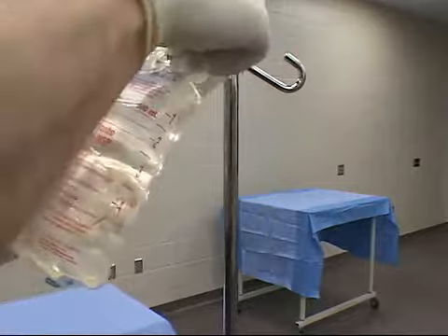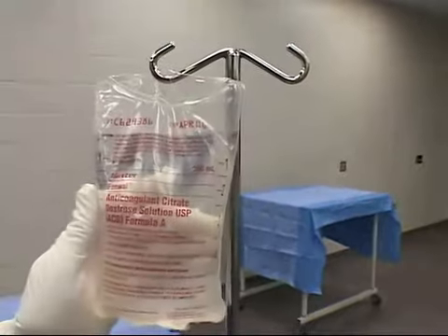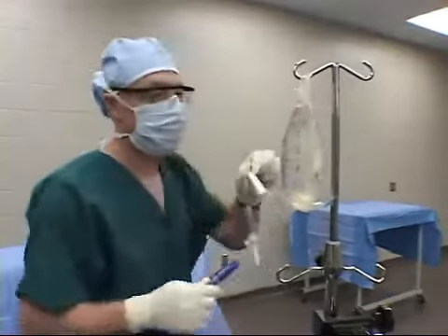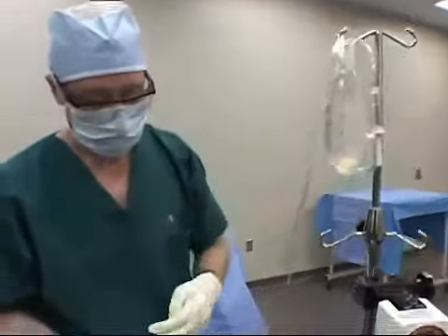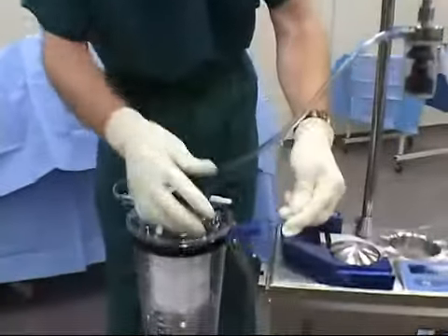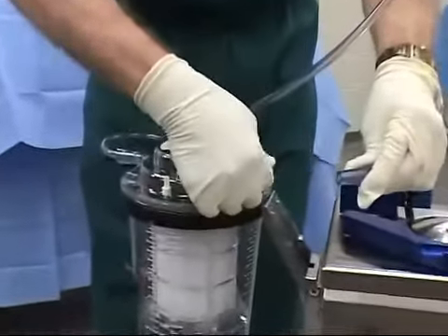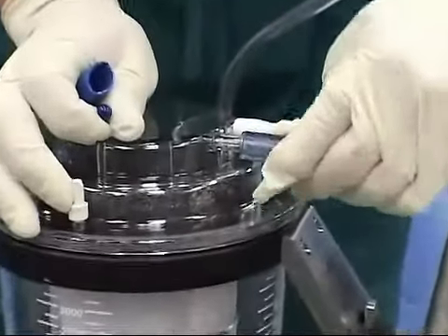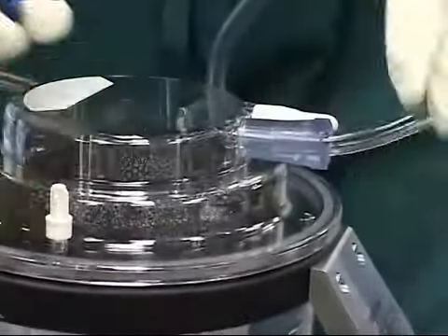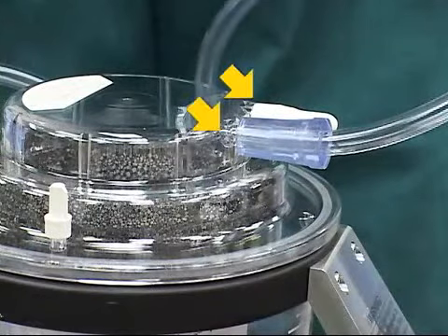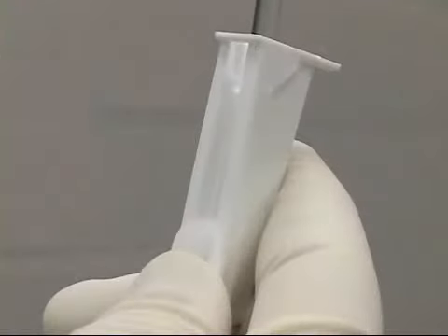Hang the anticoagulant solution on the upper IV pole. Attach the blue-capped end of the suction anticoagulant line to either the blue or the white inlet port of the reservoir. There are two inlet ports available to accommodate multiple suction lines. Close the roller clamp on the suction anticoagulant line.